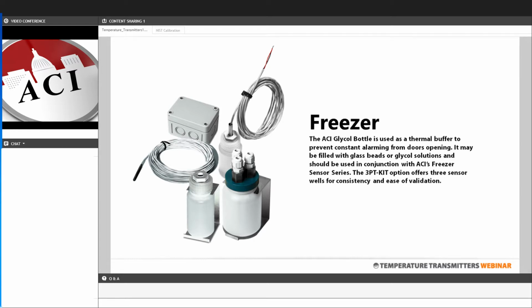However, you can fill these glycol bottles and put the sensor inside, and it acts as a buffer to slow the response time down so you can get an accurate trend of the long-term temperature changes due to system fluctuations. We have the ability to pre-fill this glycol bottle and pre-assemble the sensor into the bottle so that you can provide your customer with a complete package that's ready to install right out of the box. We fill it with a food-grade quality glycol solution. We also have these 3-port kits and bottles available for any critical applications that require multiple redundancies of the temperature sensors.